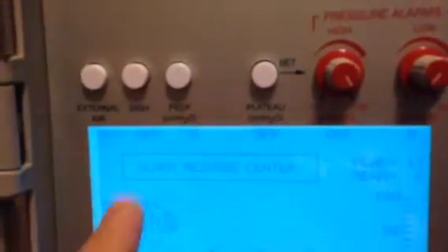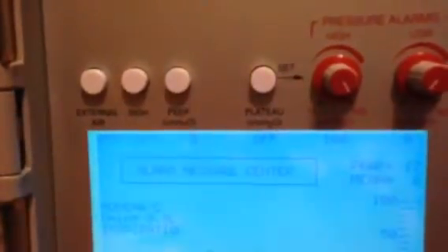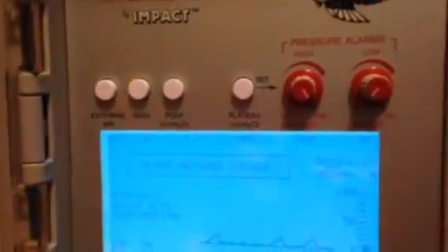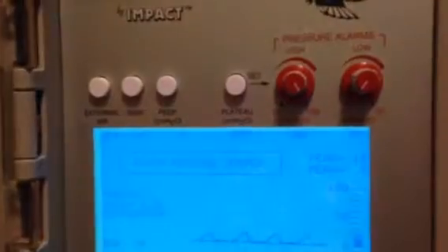And if you notice, you can only press that button and it goes up. It will go from 0 to 20 centimeters of water of PEEP. So an important thing for you to know is set the PEEP before you put the ventilator circuit on the patient, or you can encounter all kinds of problems and potentially damage lung tissue to your patient.